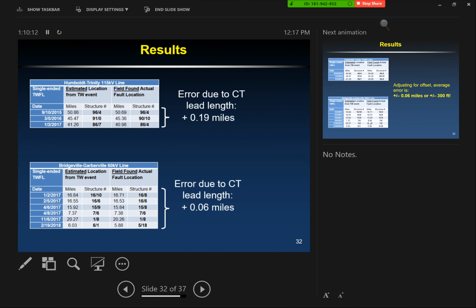That's where your CT lead length comes into play—we were not accommodating for that line extension from the CT lead length. You might think, compared to the length of the line, that's not a big deal. But light propagates down that CT lead length differently because it's covered by a dielectric and not air insulated like the primary. Light travels around 60 to 70% of speed of light along the CT lead length, so it's propagating a lot slower, and those CT lead lengths look a lot longer than they actually are.